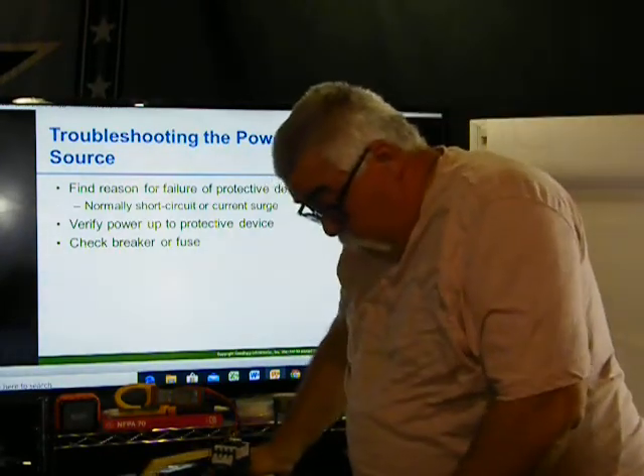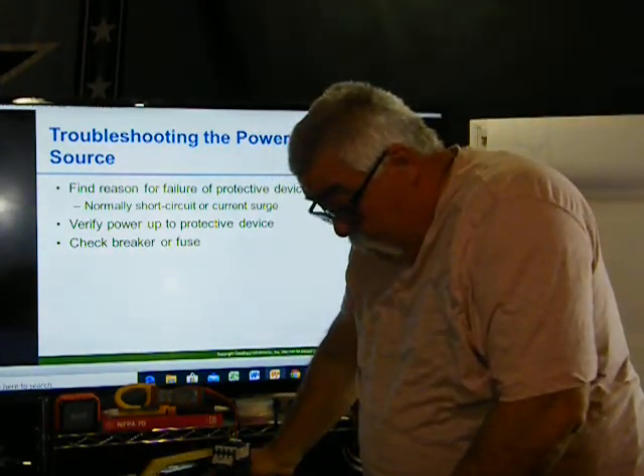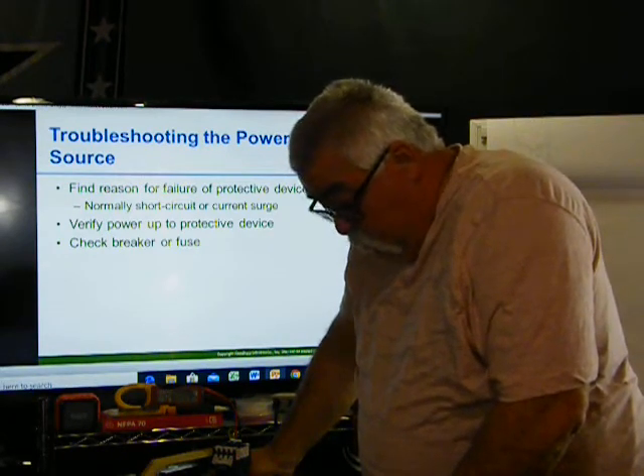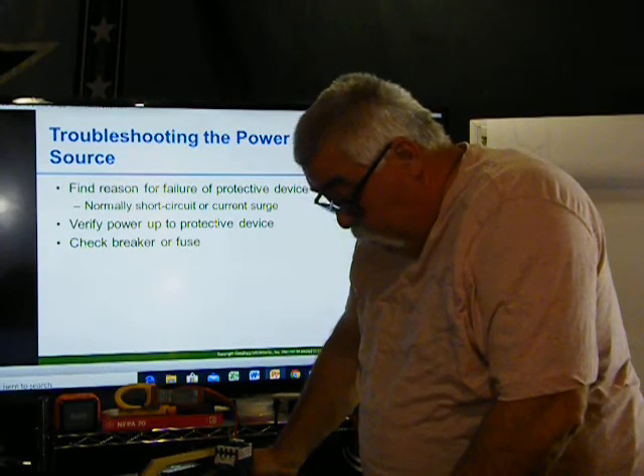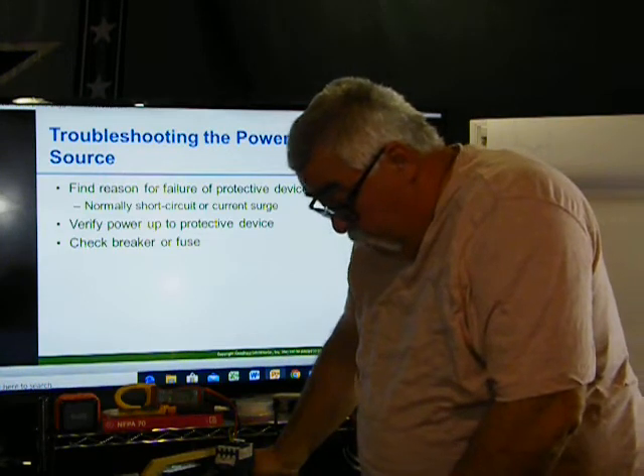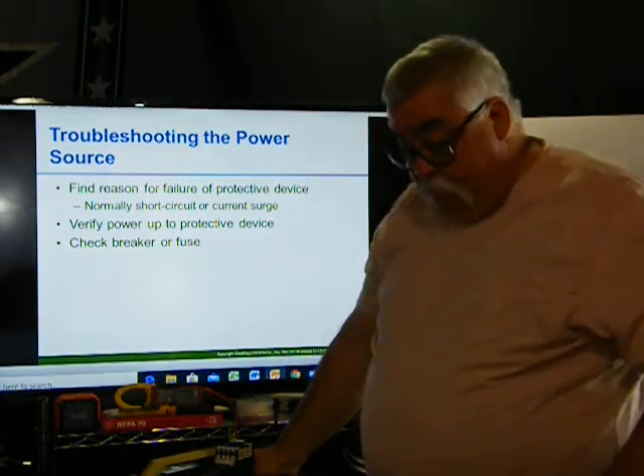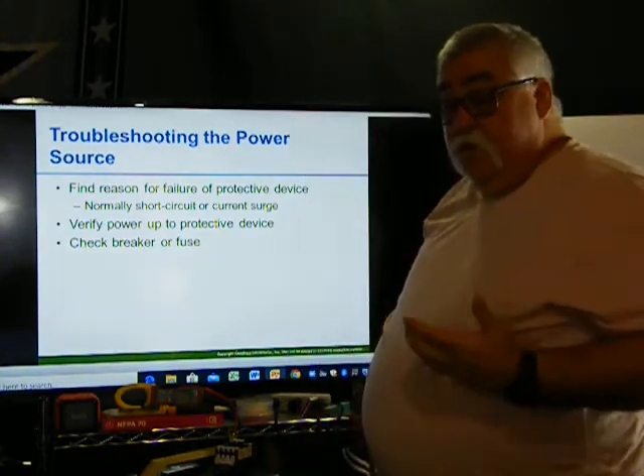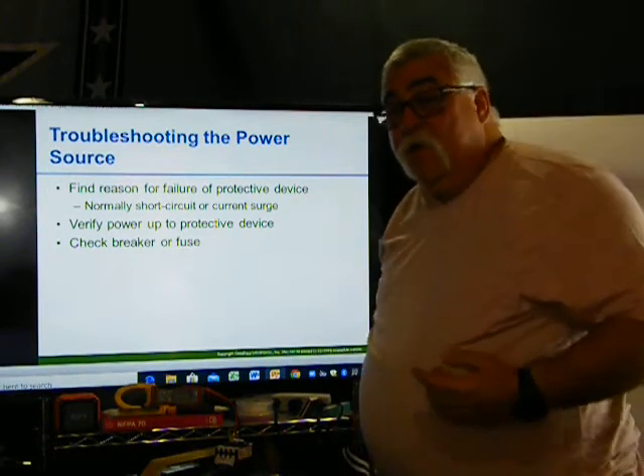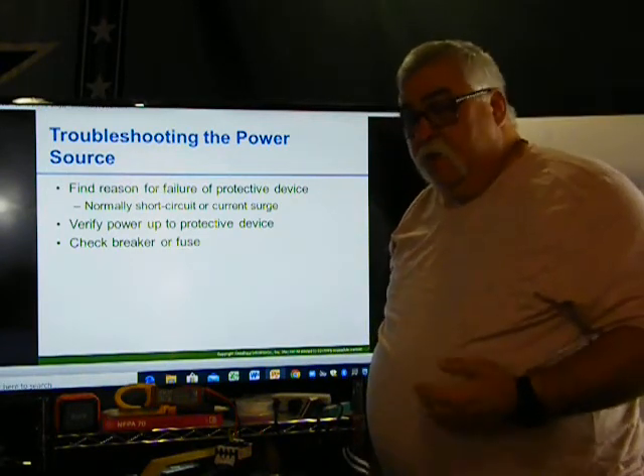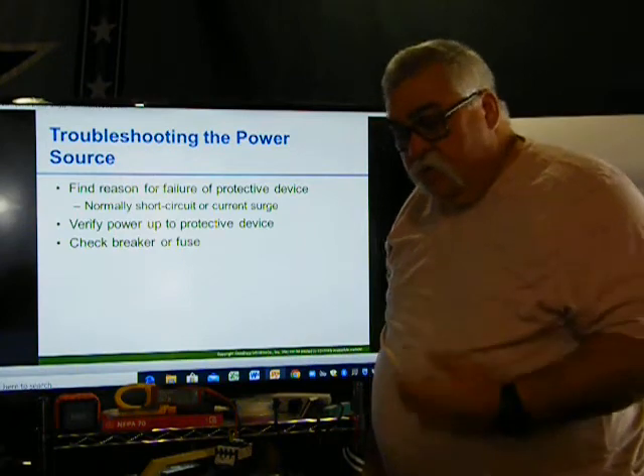It says, when a breaker may trip or a fuse may blow, creating a problem, in this case the reason for the failure of the protective device must be found. So before you turn power back on, what caused that breaker to trip? What caused that fuse to blow?